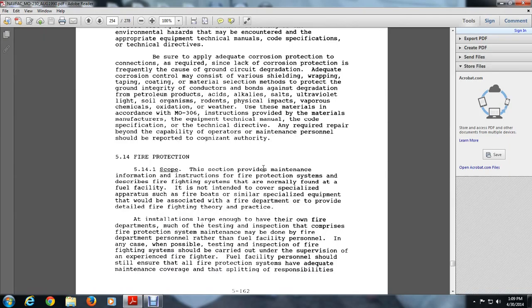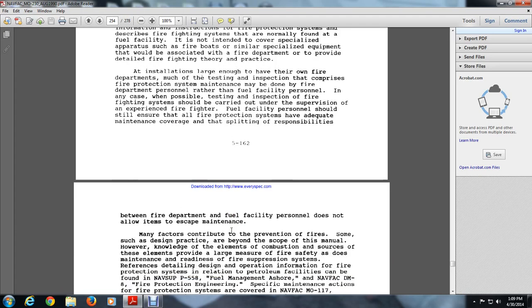theory and practice. An installation large enough to have its own fire department much of the testing and inspection of the fire protection system. Maintenance may be done by the fire department personnel rather than the fuel facility personnel. In any case, any testing, inspection, and firefighting of the system should be carried out under the supervision and experience of the firefighter and fuel facility personnel. They should still ensure that all fire protection systems receive adequate maintenance coverage, and the splitting of responsibilities between the fire department and fuel facilities personnel does not allow any items to escape maintenance.